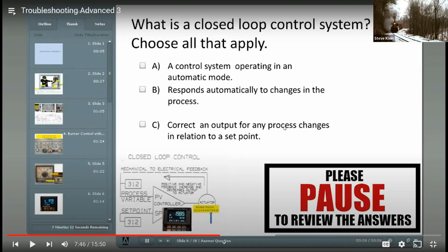So the closed loop in that case is you're getting the air signal back in to control the damper. The damper is being controlled hither or yon. I can control it all day long with my manual switch, but unless I do something with the signal that's coming back in, that's an open loop. You close the loop by putting it in auto.